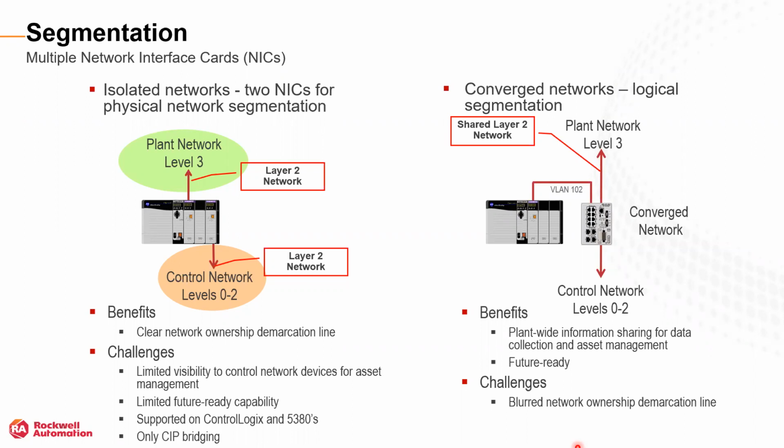I get questioned all the time when I've done layouts for people on their systems. Sometimes I will get a question like, why am I using 2 network cards when I only have a couple of banks of remote IO all tied to its own? Well, I'm trying to create a segment between the plant level network and the control network. In my mind, there's nothing on the control network, that's where our IO, our VFDs, our MCCs reside. I want to segment that from the plant network.